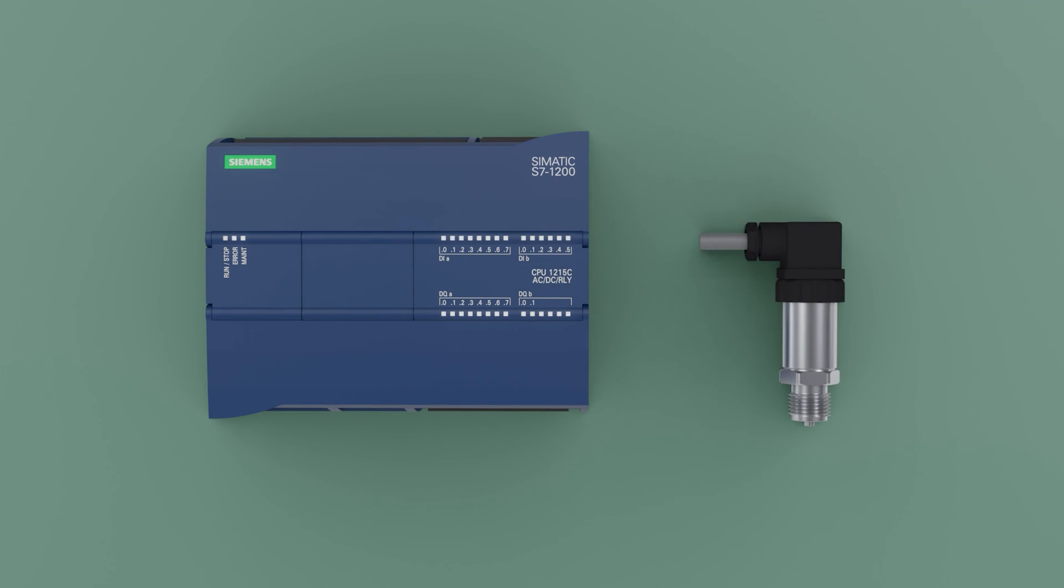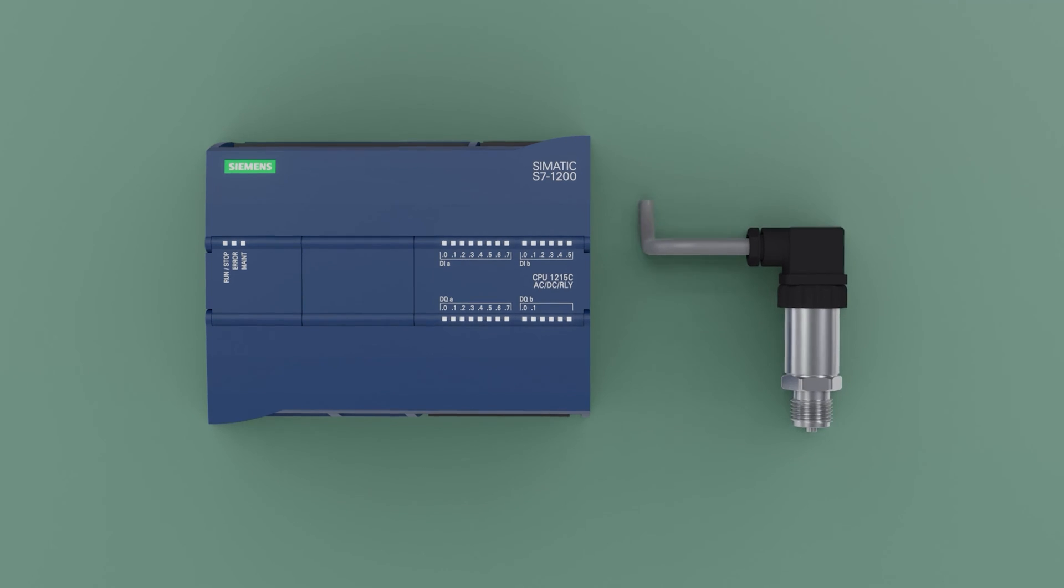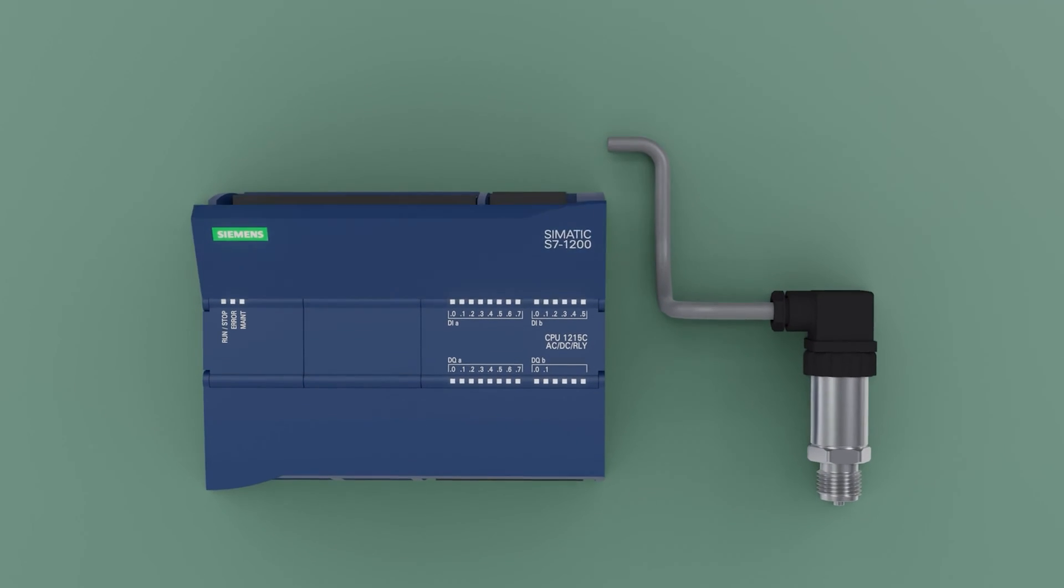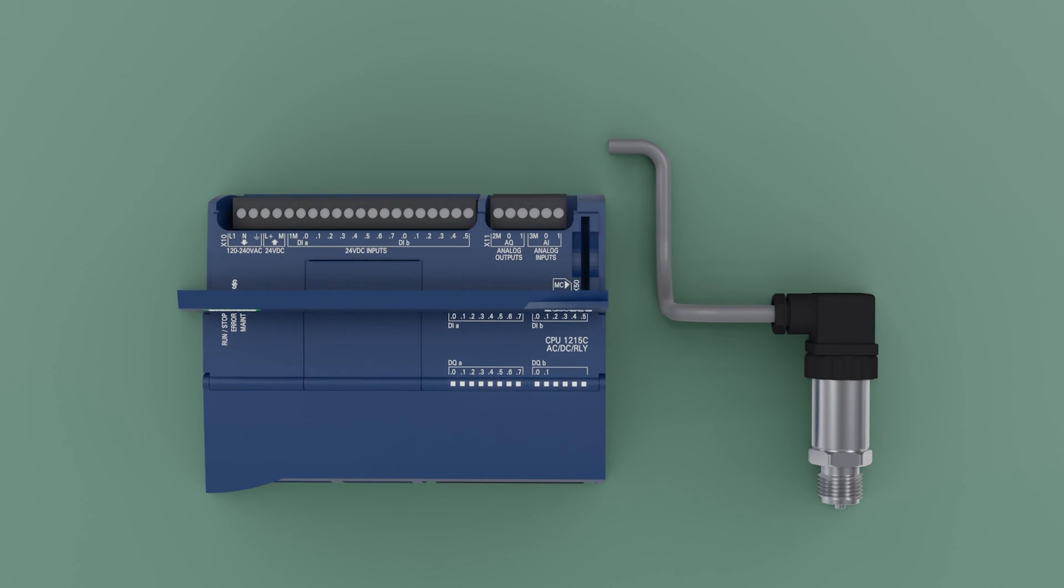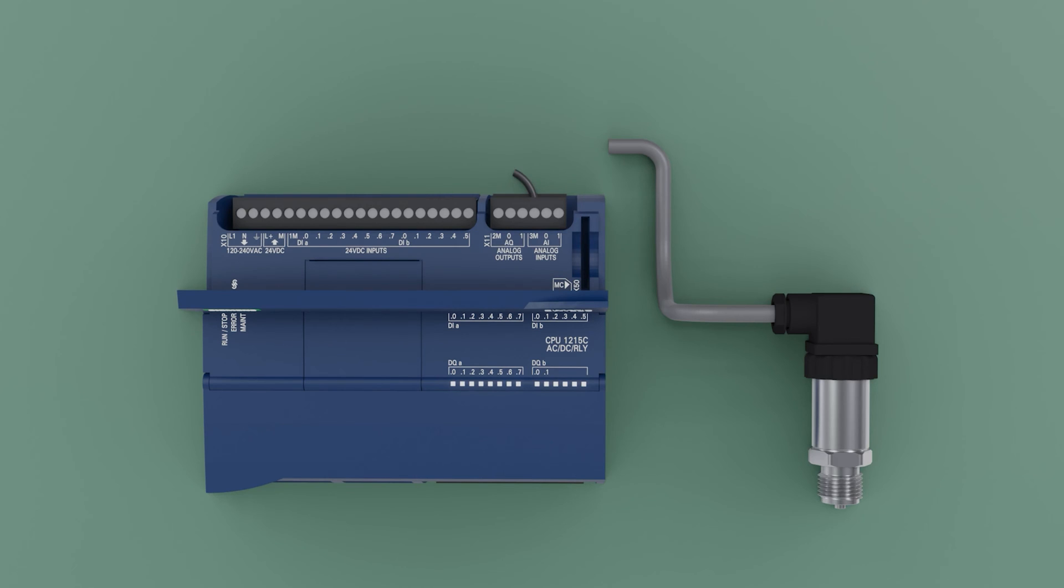Now we are going to connect the pressure transmitter to the Siemens S7-1200 PLC. This PLC has built-in analog inputs and outputs, but their inputs can only receive a voltage signal from 0 to 10 volts. We begin to join the negative of the input, the 3M, to the PLC source, to the negative M. We will connect a current pressure transmitter, 4 to 20 milliamps.